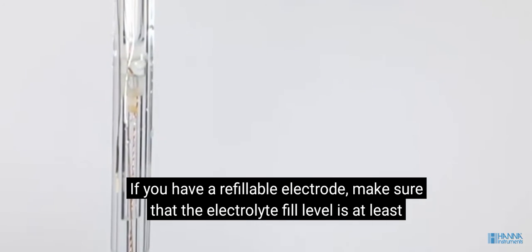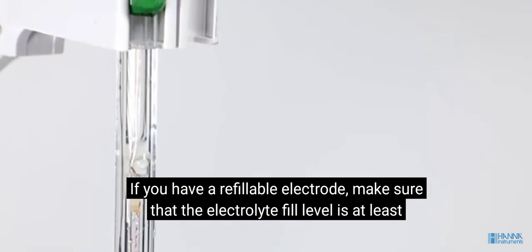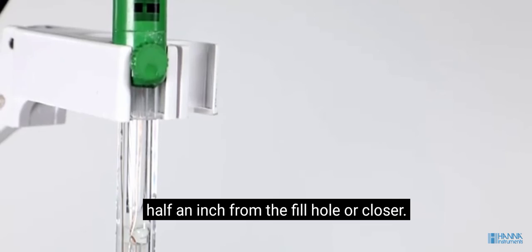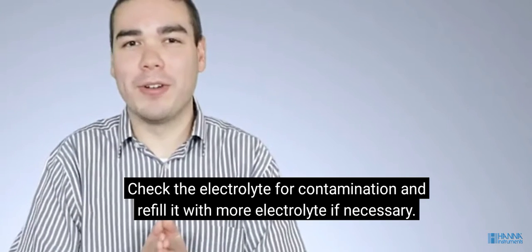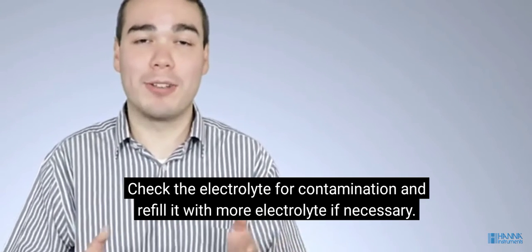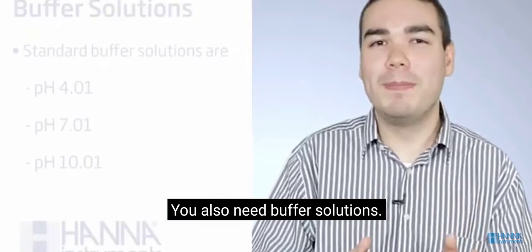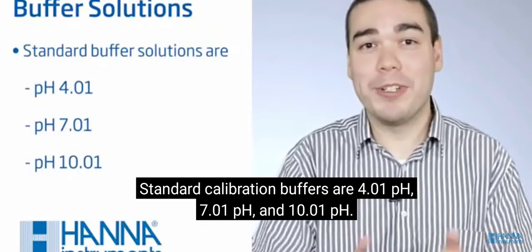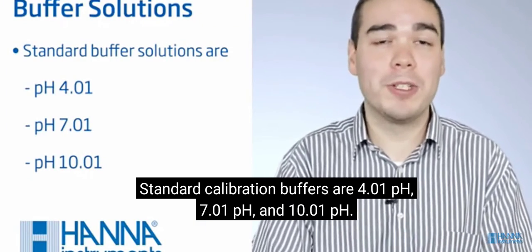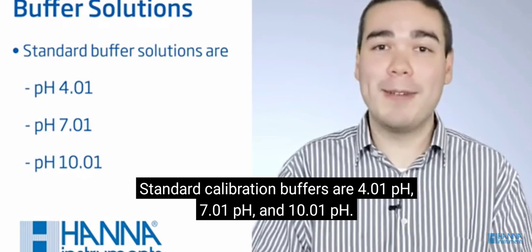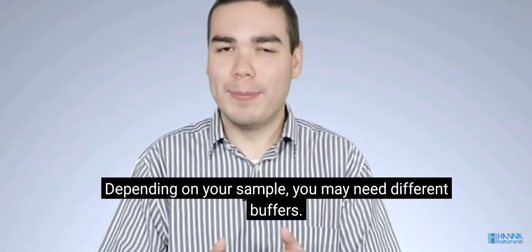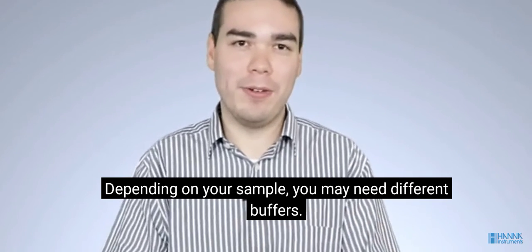Meter with your application-specific electrode. If you have a refillable electrode, make sure that the electrolyte fill level is at least ½ an inch from the fill hole or closer. Check the electrolyte for contamination and refill it with more electrolyte if necessary. You'll also need buffer solutions. Standard calibration buffers are 4.01 pH, 7.01 pH, and 10.01 pH. Depending on your sample, you may need different buffers.